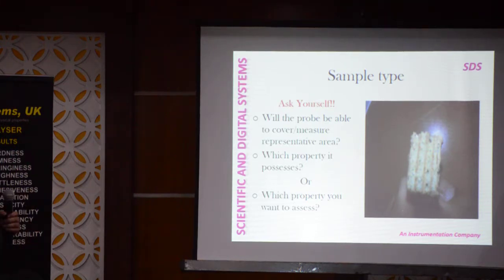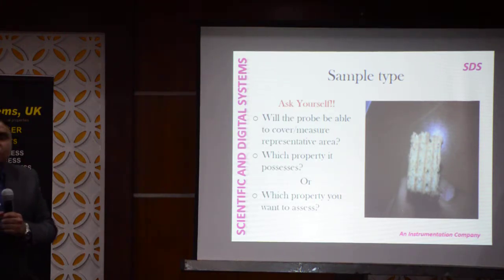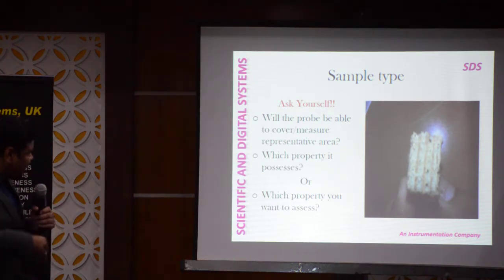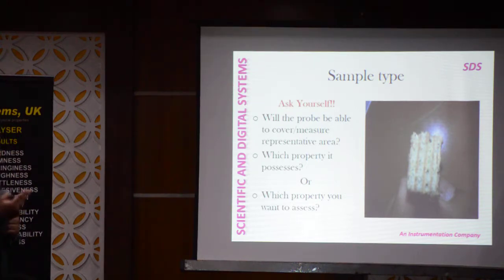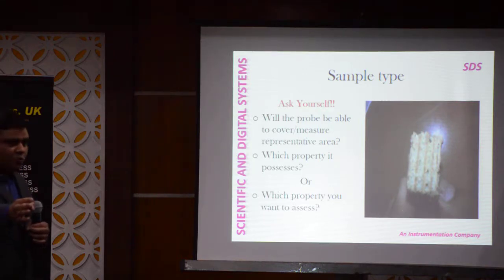Second consideration: which property does it possess? If I want to check crunchiness or crispiness of a product, I will not use a smaller probe — I will use a bigger probe, or do multiple punctures or a multiple cutting test, because my objective is to test crunchiness, not just the hardness of the bar. You need to decide whether you want to assess hardness of the surface, structural hardness of the whole bar, or crunchiness. It all depends on your requirements — it is you who decides, not the machine.